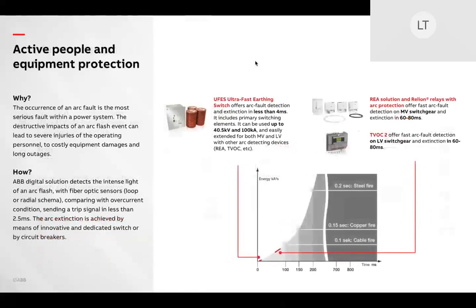So, why should you do this now? The answer is simple. Arc faults are the most serious fault within your power system. The cost, both to life and equipment and outages, are real. Our solutions can extinguish an arc fault in less than 4 milliseconds in the application of the ultra-fast acting earth switch, and between 60 to 80 milliseconds using arc protection Relion relays, including the switching time of the breaker.